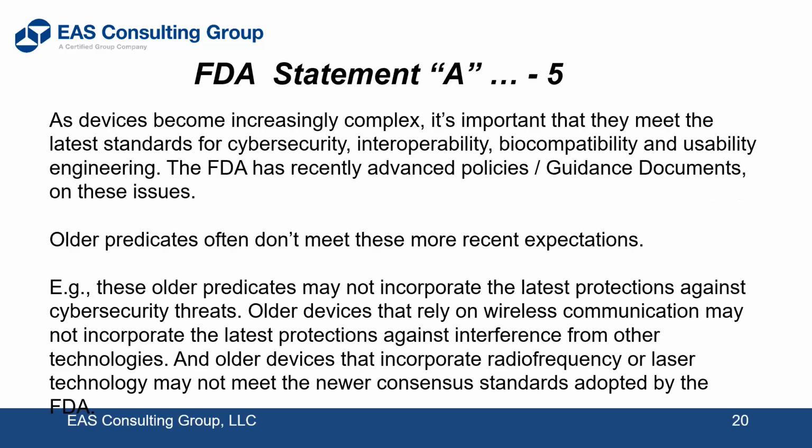Now you notice here, as devices become more complex, they have to meet standards, and there are guidance documents on them right now on cybersecurity, data integrity, usability engineering, that's IEC 62366-1, biocompatibility issues, et cetera. Use engineering, we mentioned that. Cybersecurity is a growing issue if your product can be networked in any way, shape, or form. It has software in it, and it can or is networked to the internet where it can be compromised.